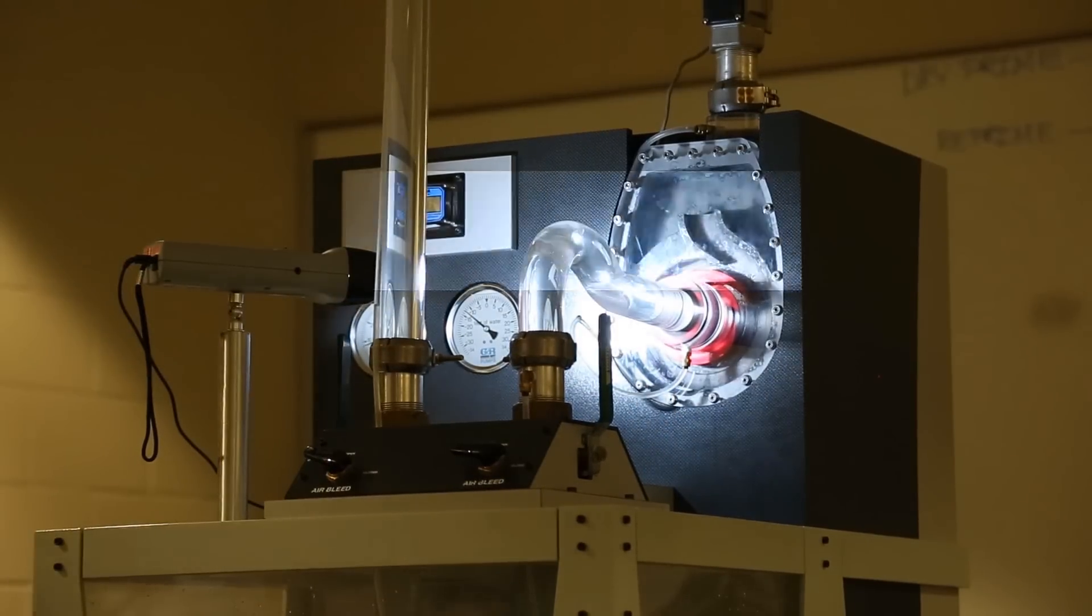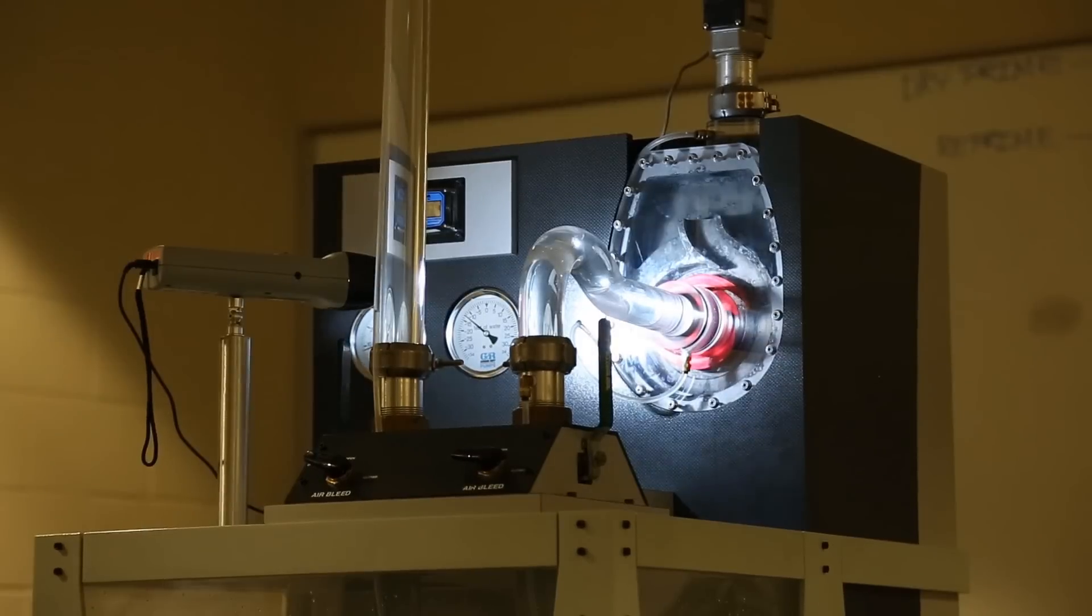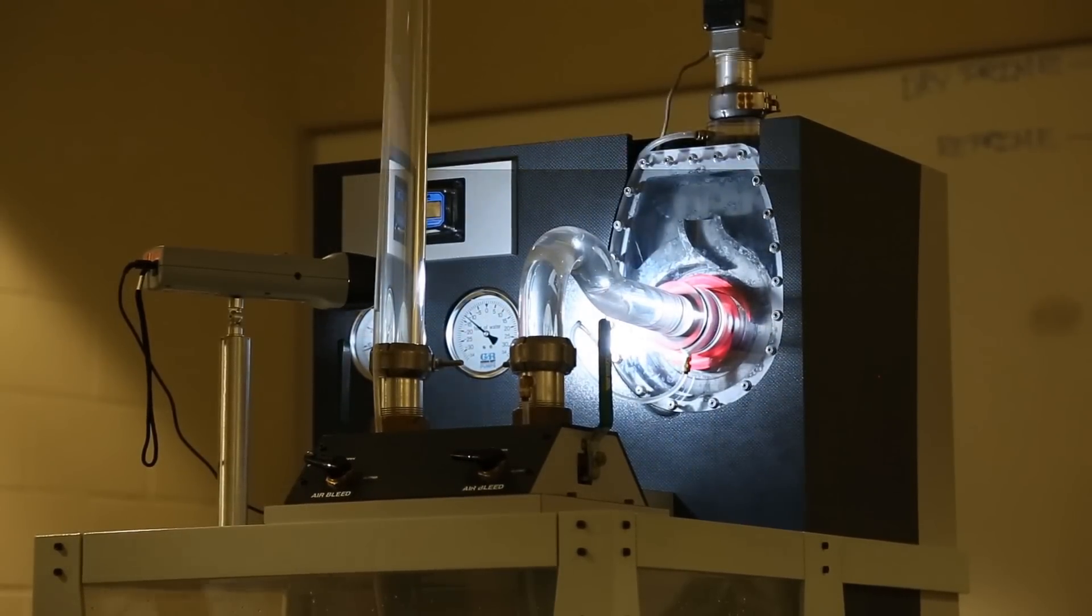You get an impeller where the tips of the impeller look fine. There's nothing wrong with the tips at all. But if you look in there at the eye, you've got little chunks of metal blowing away at the eye.